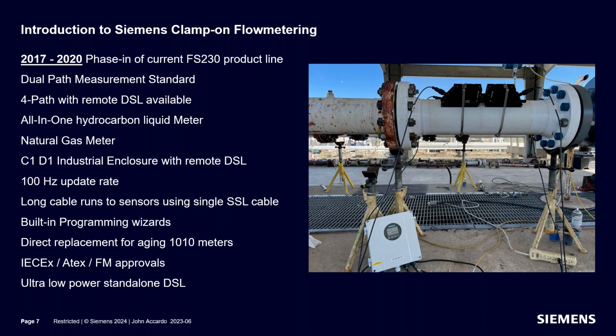In 2017 through 2020, the first models of the FS230 system were introduced. This was the first meter that was fully engineered by Siemens. There was obviously a lot of old Controlotron personnel involved in the development, but under the Siemens banner, this was the first release of a fully Siemens designed flow meter. Along with the FS230 came a dual path as standard.